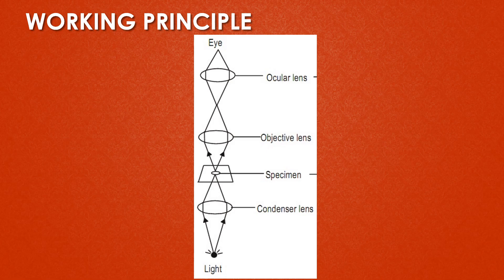This is the working principle and the flowchart of the bright field microscope. First is the light source. The light from the light source is aimed towards the lens beneath the stage, called the condenser lens. This condenser lens condenses the white light and passes it to the specimen. From the specimen, the light passes through the objective lens, then to the eyes through the second magnifying lens called the ocular lens or eyepiece, and finally we visualize the image of the given specimen.